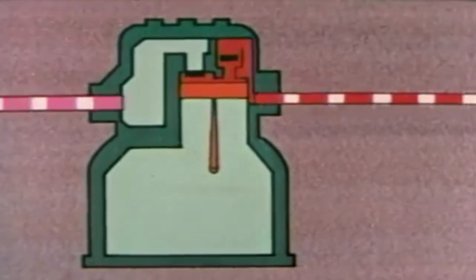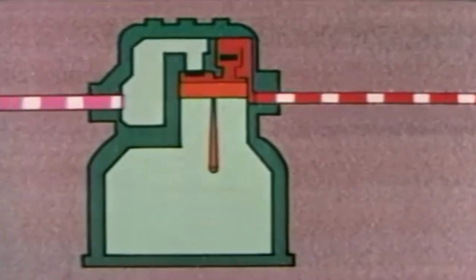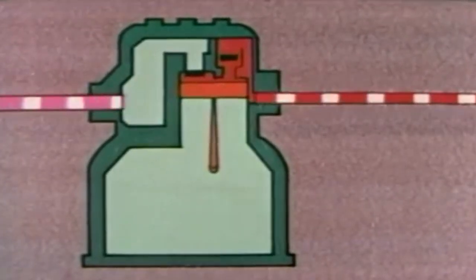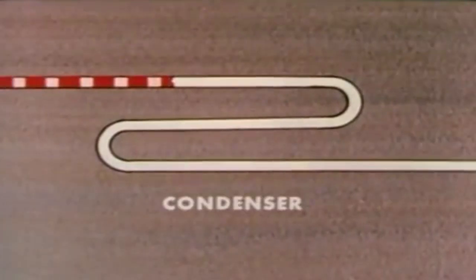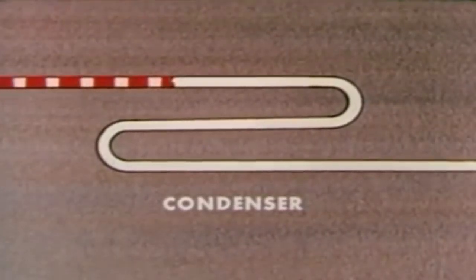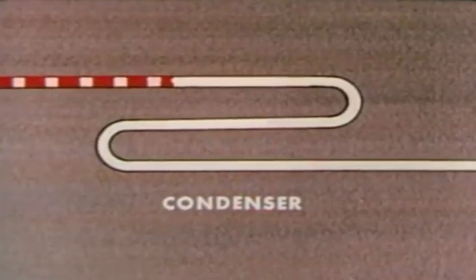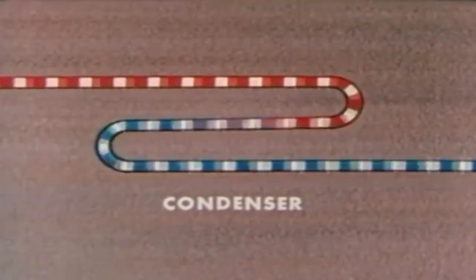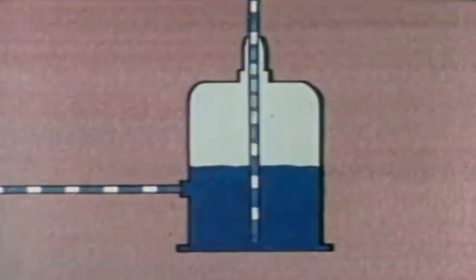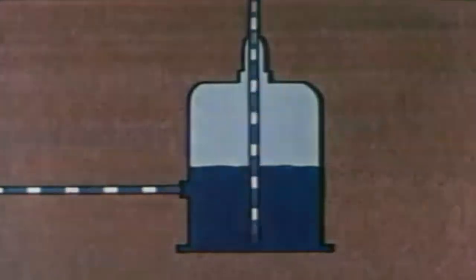Remember what happens when gas is compressed? Pressure goes up, temperature goes up. The gas, now at high pressure and high temperature, flows into the condenser. The gas is hot — hotter than the surrounding air — so it gives up heat to the air. As the refrigerant loses heat, it starts changing back into a liquid. To complete the cycle, the liquid refrigerant returns to the receiver.